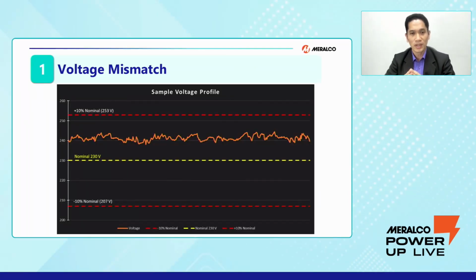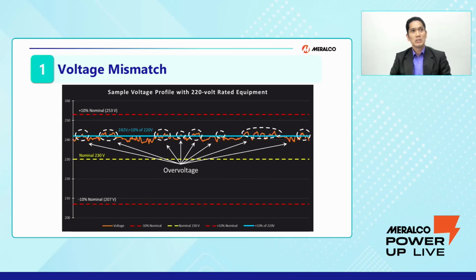For the example voltage profile, we can see here the upper and lower broken red horizontal lines, which are the allowable voltage variation at 230 volts. The upper line is plus 10% of the 230 volts nominal, or 253 volts, while the lower broken red line is minus 10%, or 207 volts. The 230 volts nominal is represented by our yellow broken line. In case we have a 220 volt rated equipment, plus 10% of the 220 volt rating is 242 volts.